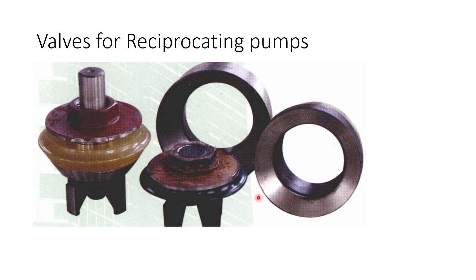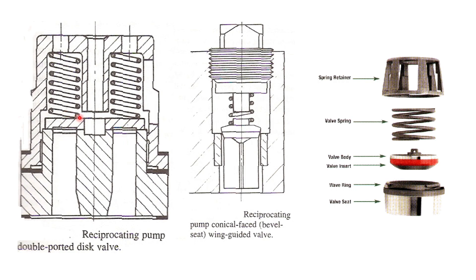Now let us see some valves used on the reciprocating pump. Both the suction and discharge valves of the reciprocating pump are non-return valves. The suction valve opens inside the pump and the discharge valve opens outside the pump. This is the valve which sits and does the sealing. This is the metallic type. There are different types of valves used. Here, this is called a double ported valve — it has two ports and is a disc valve loaded with a spring. The spring closes the valve and the pressure of the fluid opens the valve.